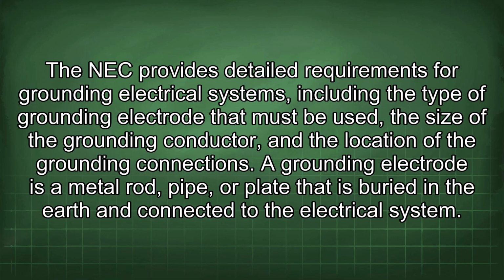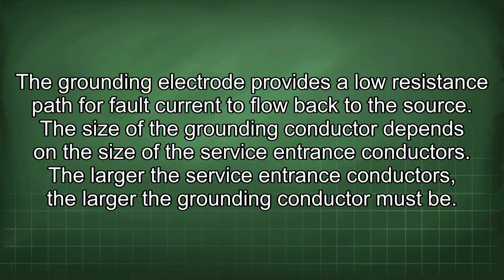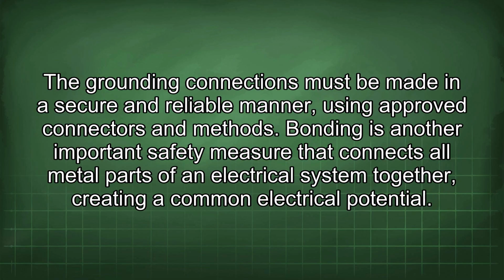A grounding electrode is a metal rod, pipe, or plate that is buried in the earth and connected to the electrical system. The grounding electrode provides a low resistance path for fault current to flow back to the source. The size of the grounding conductor depends on the size of the service entrance conductors. The larger the service entrance conductors, the larger the grounding conductor must be. The grounding connections must be made in a secure and reliable manner, using approved connectors and methods.